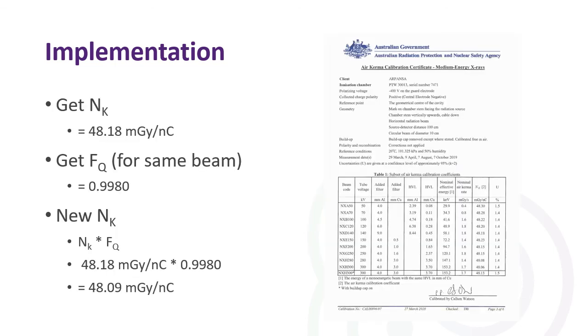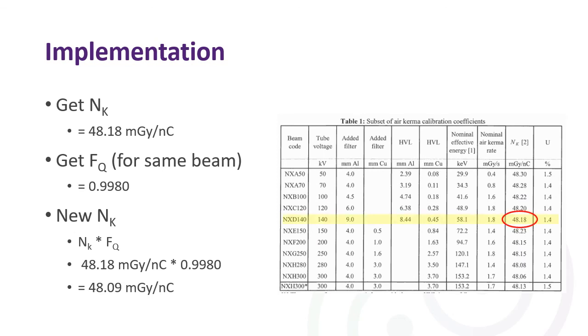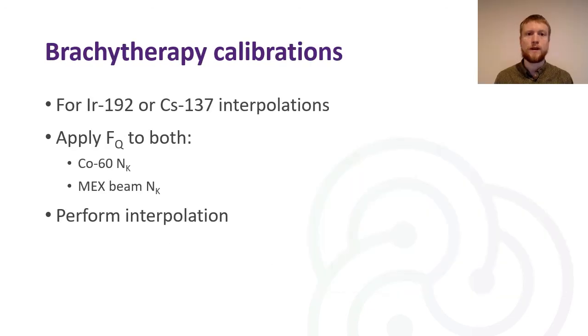So to do this, you'll get your NK value from your report. So if we zoom in on this table, have a look at that beam, there's the NK for this beam. Get the FQ from the same beam from the report that we'll be publishing and multiply those, and you can see there that you have your new NK value for this beam. For brachytherapy calibrations for iridium or for cesium interpolations, you would apply the FQ to both the cobalt 60 NK and the MEX beam NK and then perform your interpolation as usual.